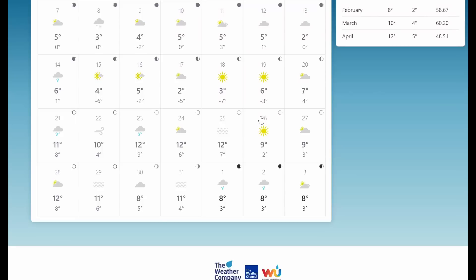For context, our design temperature here on the south coast is minus 1.8 degrees. If you don't know about heat pumps, that's the outside temperature at which they designed the system to run efficiently. So the heat pump should be able to run consistently at minus 1.8 degrees and be efficient and comfortable. But we have plenty of days way below that. Our weather app told us that on Thursday the 18th we woke up to minus 8 degrees, which was absolutely unheard of for Southampton. I was kind of excited to push the heat pump and really put it to a true test — after such a mild November and December, we didn't really get to see what it was capable of.